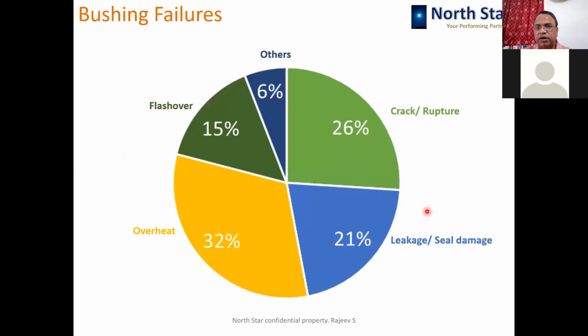Okay, if you look at bushing failures, this pie chart shows the different reasons for bushing failures. 32% of cases are because of overheating of the bushing. Why should a bushing overheat? Primarily because of poor contact, or loosening of the contacts, cables or joints, which increases the local contact resistance, and overheating happens. Another reason could be a high load on the transformer, which will also make the bushing overheat.